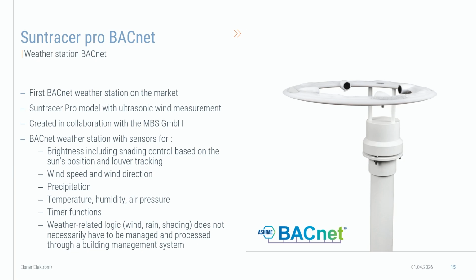The BACnet weather station is classified as B-SS, the BACnet smart sensor, and transmits the measurement data directly on the bus in a standardized format to the BACnet network. This is the real benefit: we don't need any additional gateway on the telegram line, which is good news for the market. We have reliable hardware equipped with a new interface, so we can now adapt the building automation top level with this device. That's, in principle, what it is.